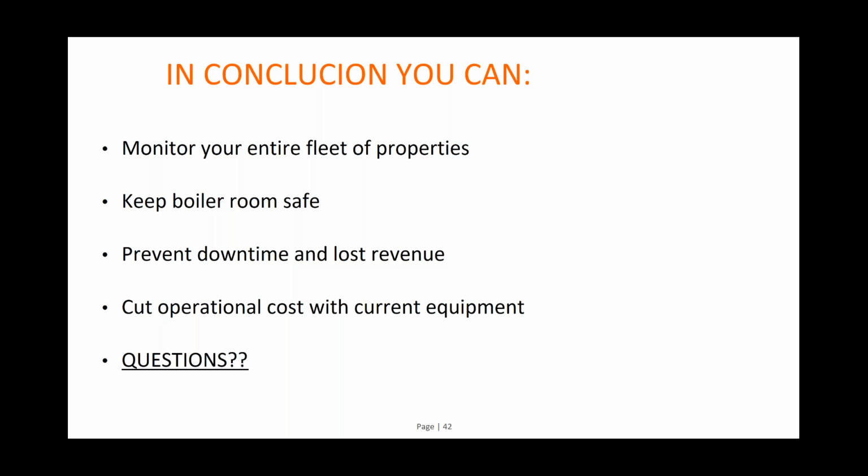Okay. Is there any example of, let's say, 90% that you could predict a failure with an electrode, for example? Have you been able to measure that? We are in the process. There are some items we are really, really good at: electrode, bearing life, failure to ignite, number of firing cycles. Those are the items that we are really, really good at.